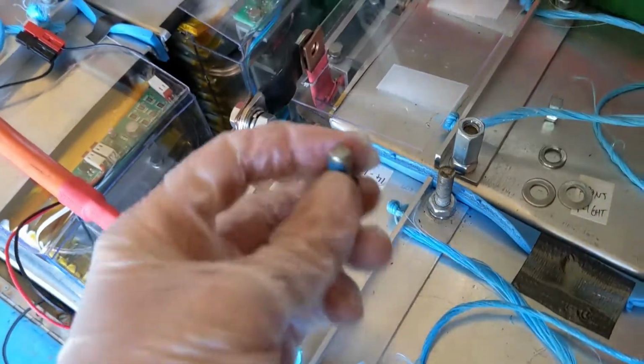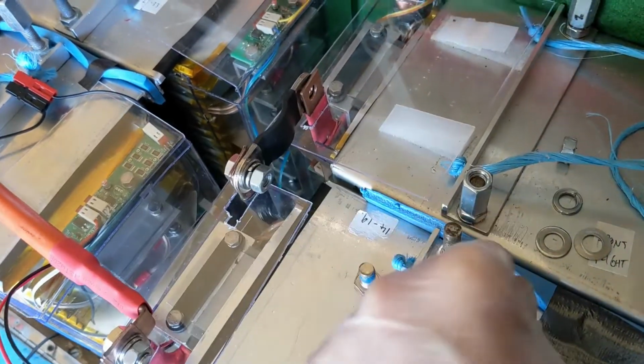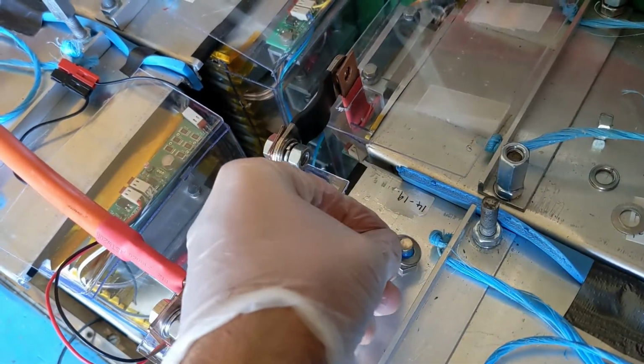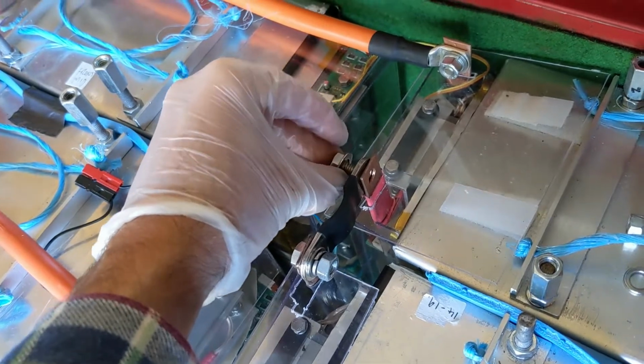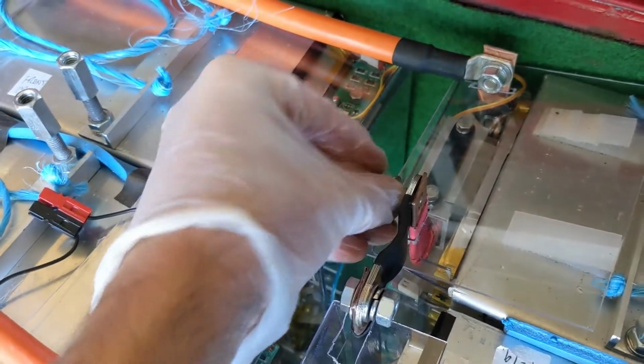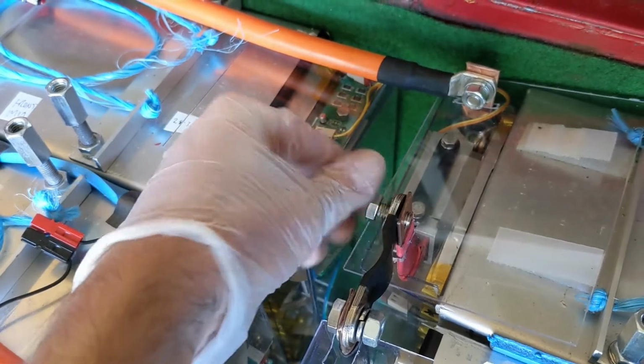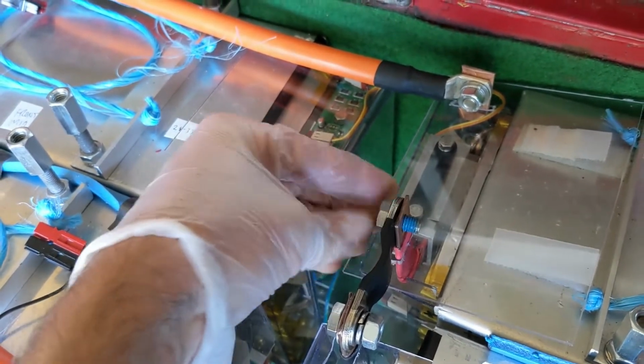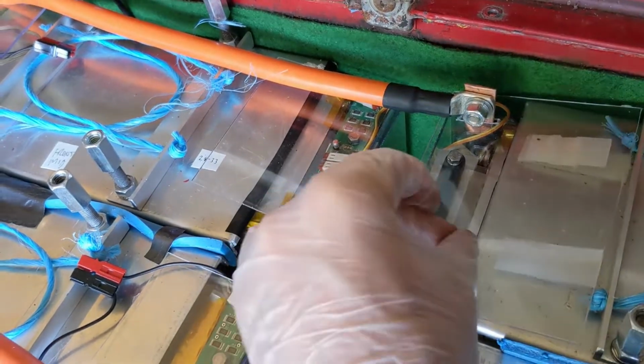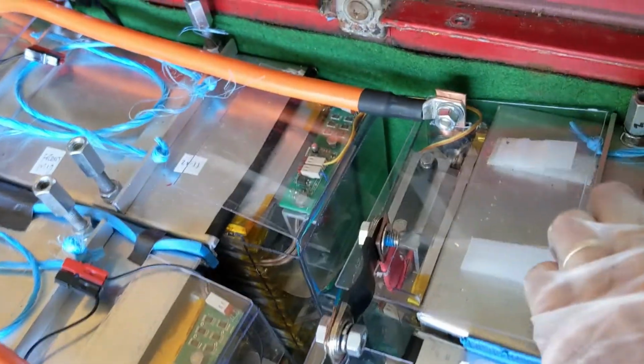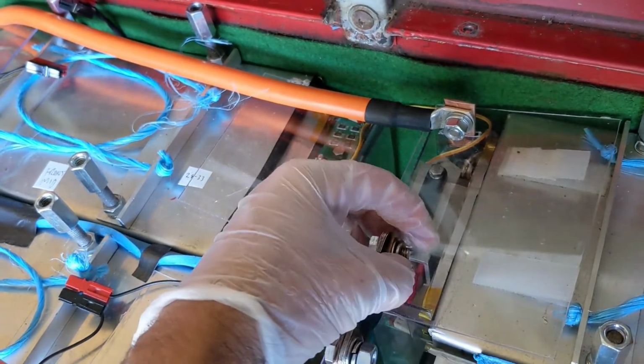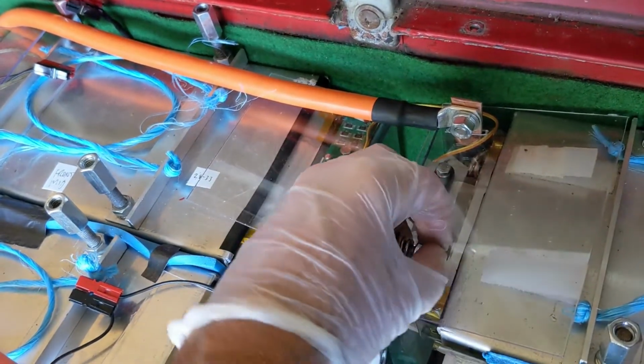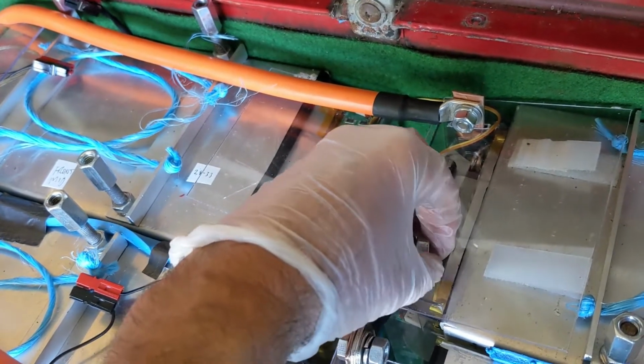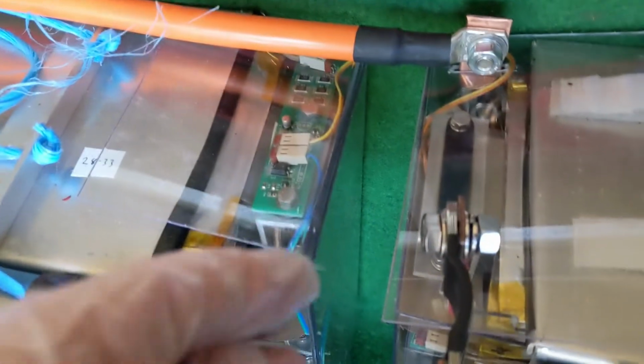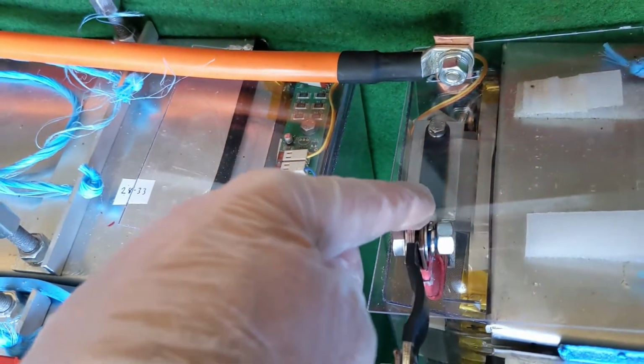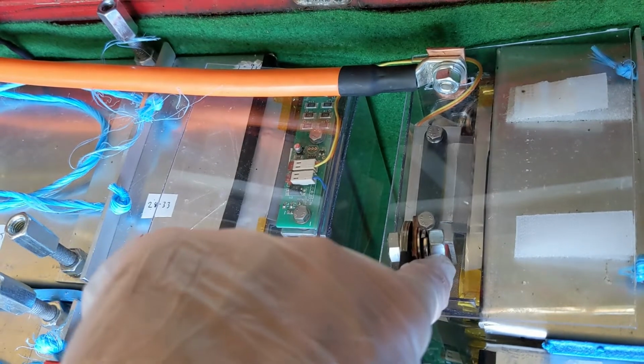With these connections, I've got these little bolts. I'm putting a flat washer on one side, put that through like so, then another flat washer and a spring washer, and then a nut. So we have bolt head, flat washer, conductor, conductor, flat washer, spring washer, nut.